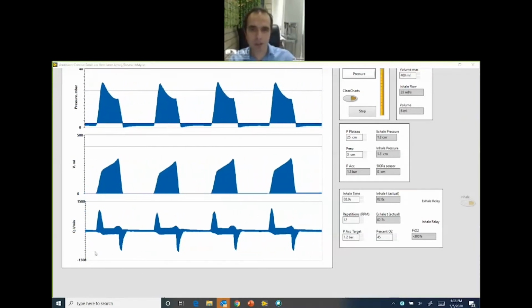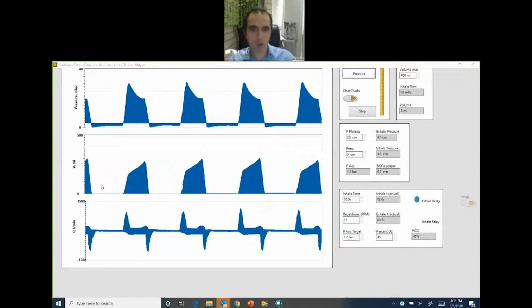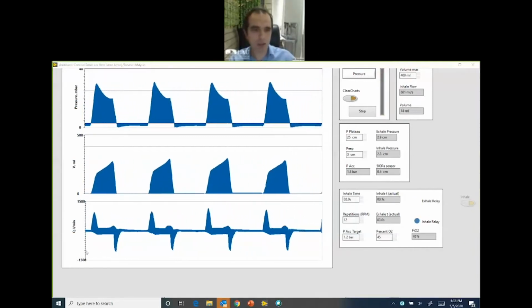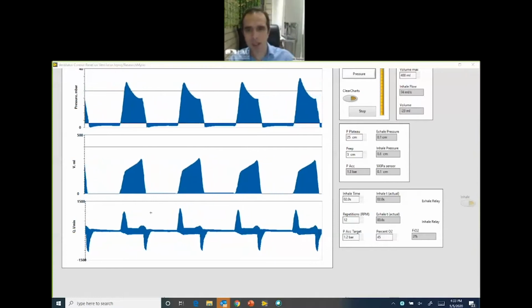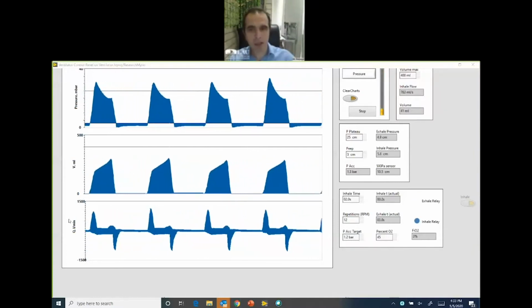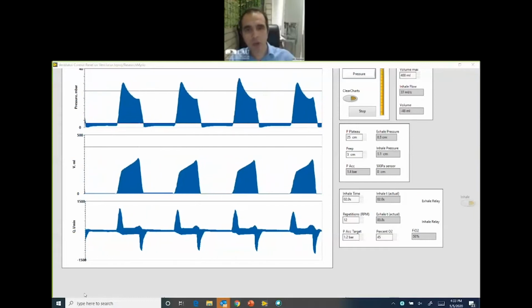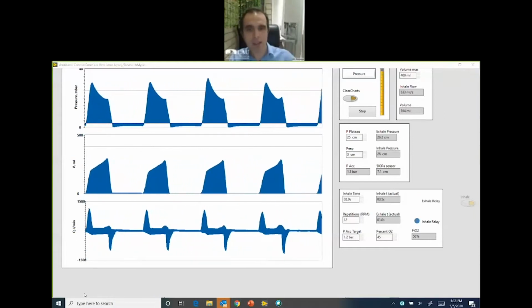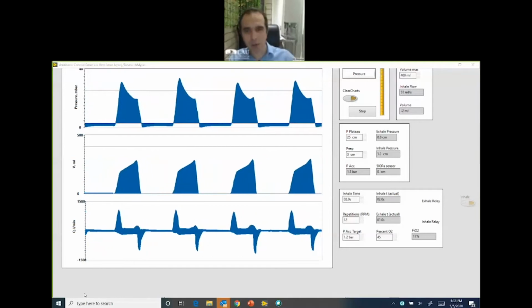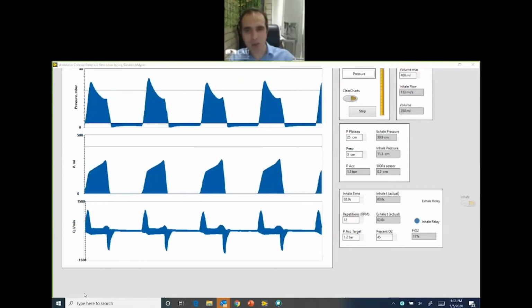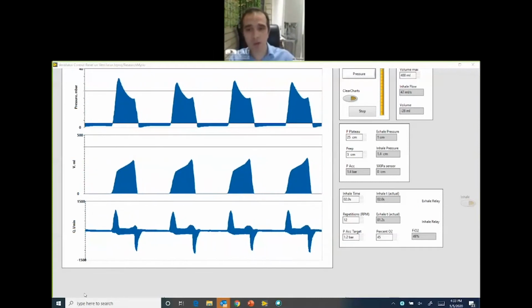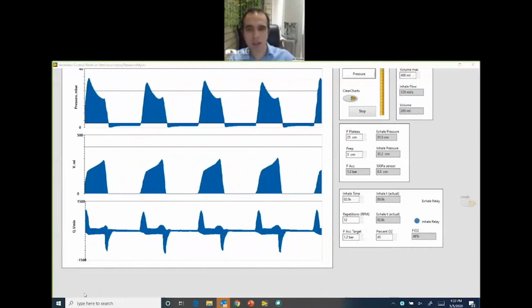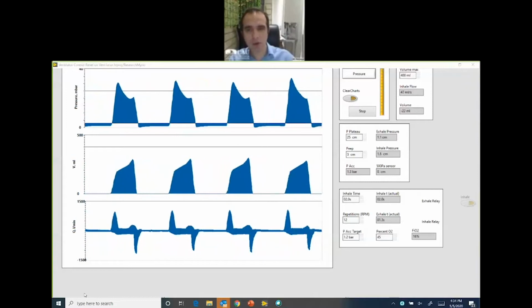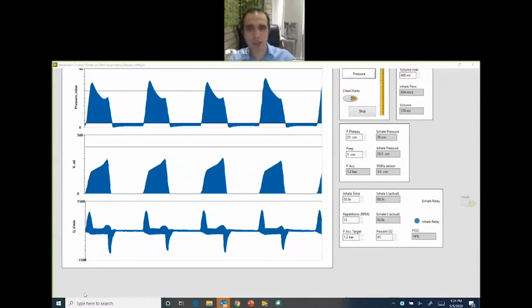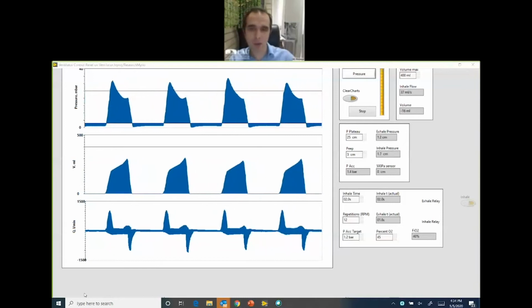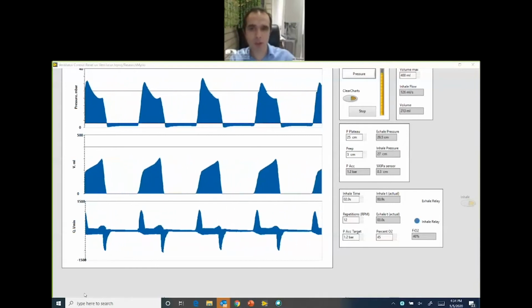Okay, so this summarizes all the components inside the ventilator. We have the pressure regulators, and an important part we're going to talk about is the algorithms: how do we control and how do you instrument this system. If you look at the components, we only have solenoid valves and a servo. The solenoid valves are controlled from the controller. Right now we're using a standalone off-the-shelf controller called myRIO from National Instruments. The myRIO will control when and for how long each one of these solenoids opens.